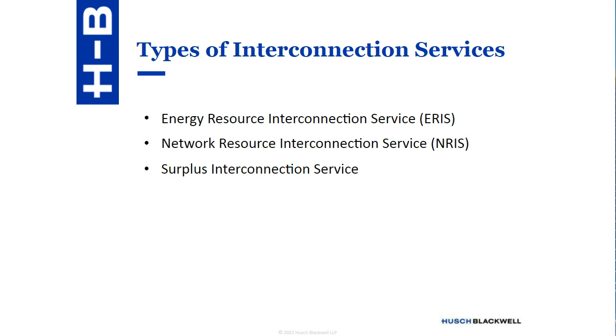Energy Resource Interconnection Service means an interconnection service that allows the interconnection customer to connect its generating facility to the transmission provider's transmission system to be eligible to deliver the generating facility's electric output using the existing firm or non-firm capacity of the transmission provider's system on an as-available basis. That is key: it's using the existing system on an as-available basis.